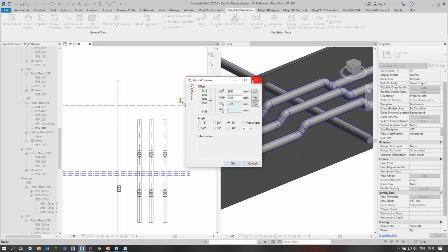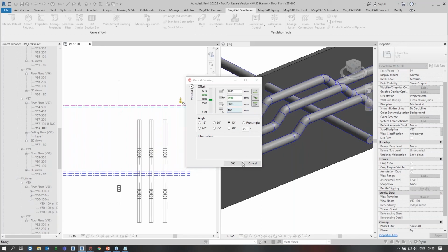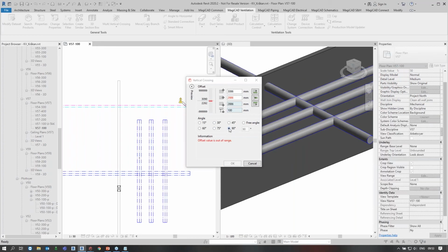Let's say that I want to have a tolerance of 100 mm between the top of one duct and the bottom of another duct. Can I do this with 90 degree bends? No, it says offset value is out of range because the height difference is too small, so I can't fit 2 90 degree bends. MagiCAD says no, you can't do it.